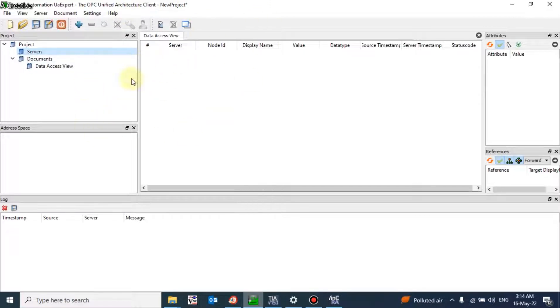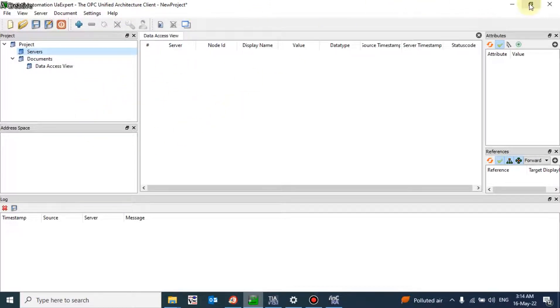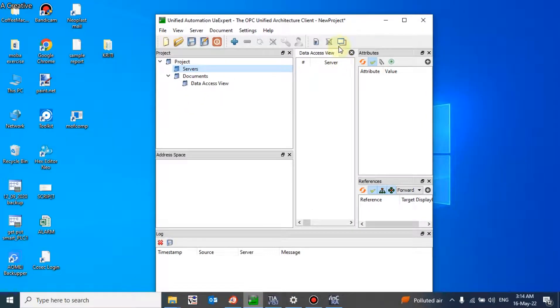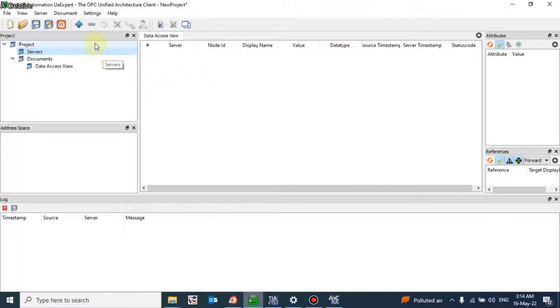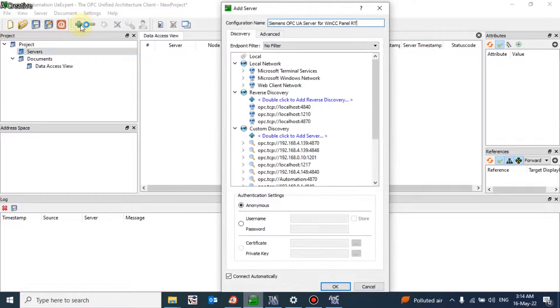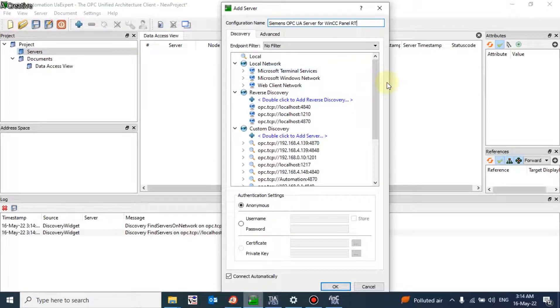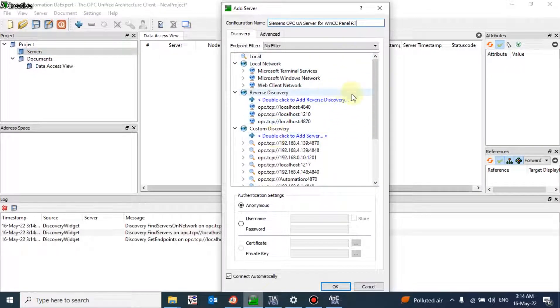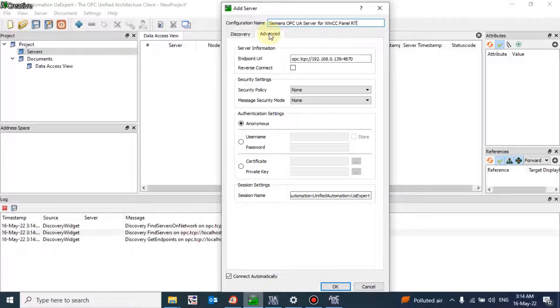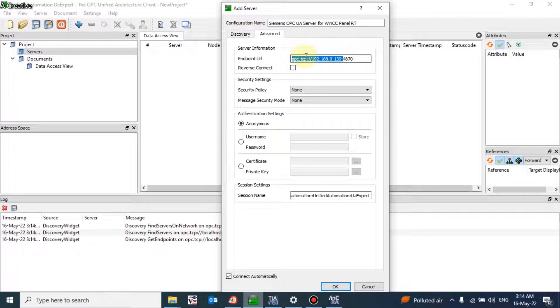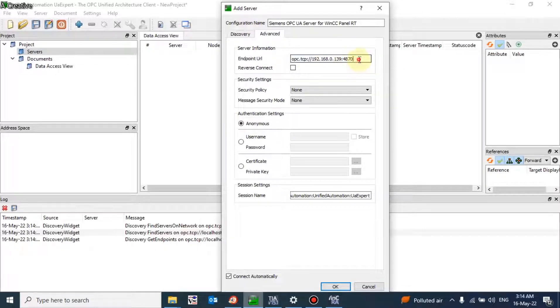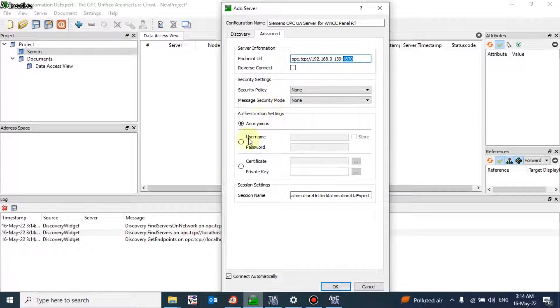This acts as an OPC unified architecture client which is widely used for testing purposes. This is our client. Now to create a server or to link with the server, we will add a server here. There are a lot of servers available. Go to the advanced and you have to mention your address here: OPC TCP 192.168.0.139 and this is my port address. There is no security we have provided. Press OK.